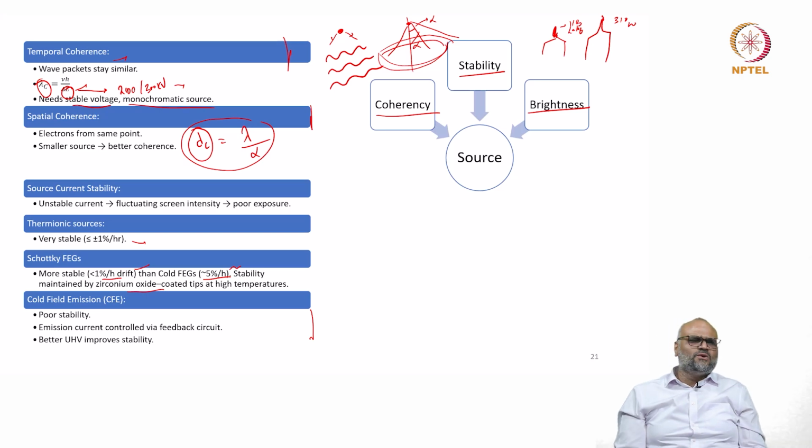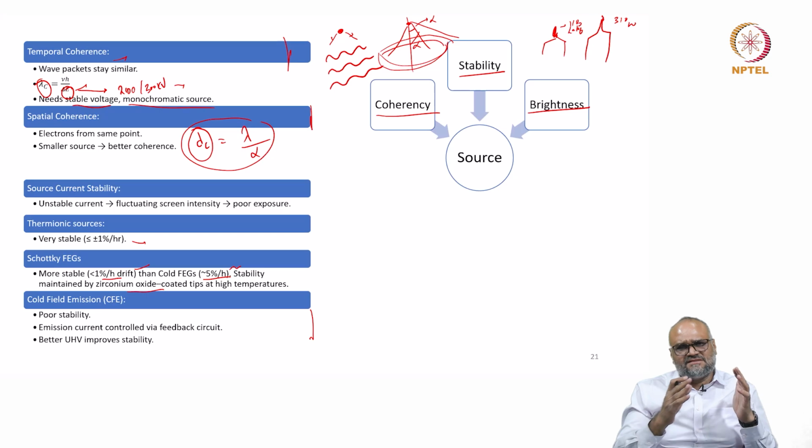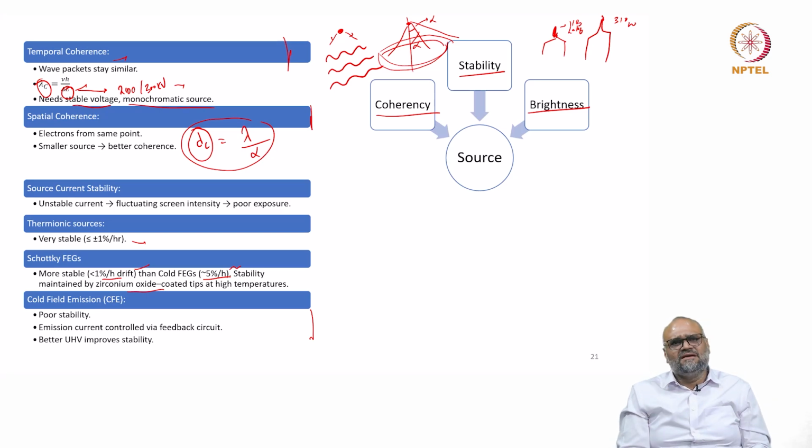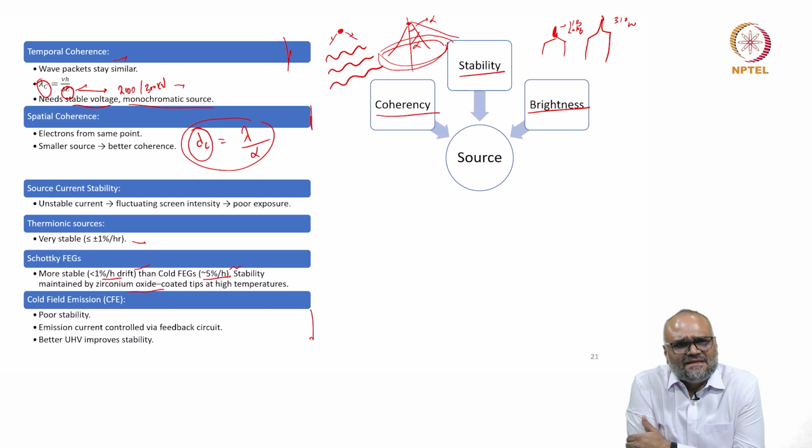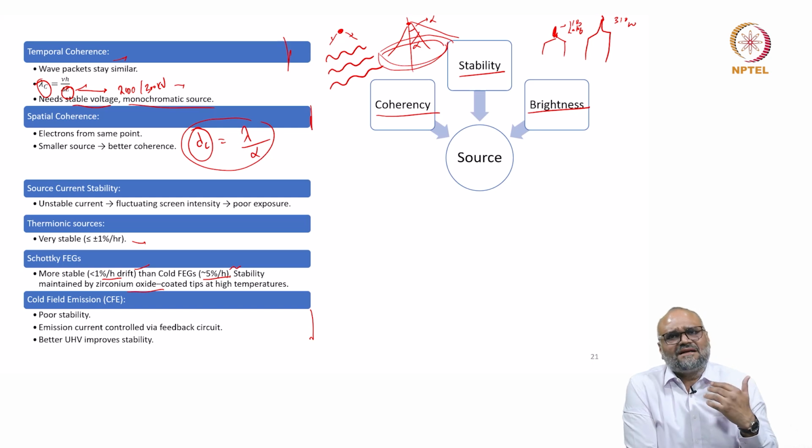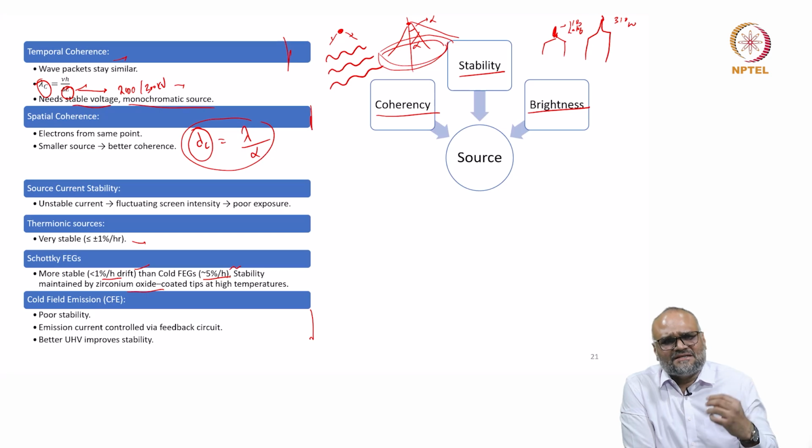So if I'm trying to do an experiment where I'm recording an in situ movie over a large period of time, please bear in mind that I would prefer stopping the experiment after 2 to 3 hours. I should do a flashing of the filament again in a cold field emitter and go back to the emission currents with the values that I get at the very start when I have a flashing.